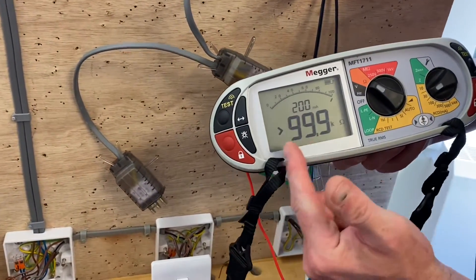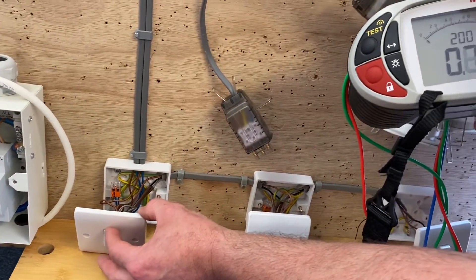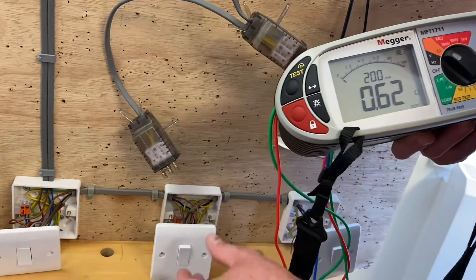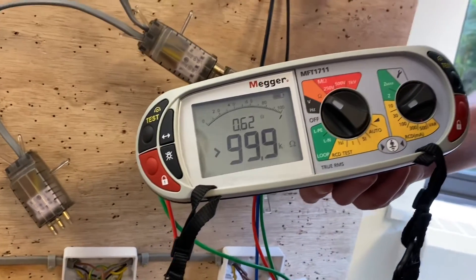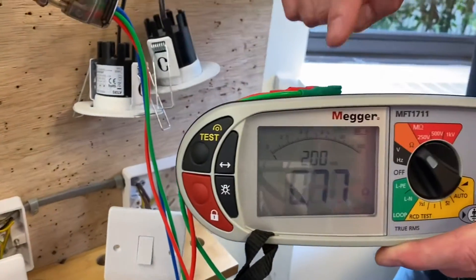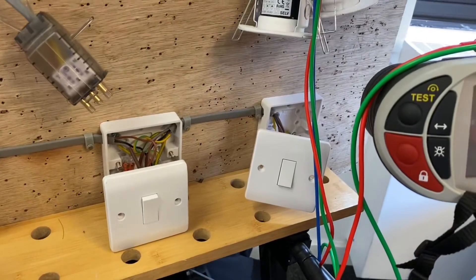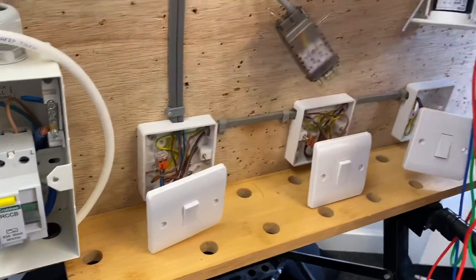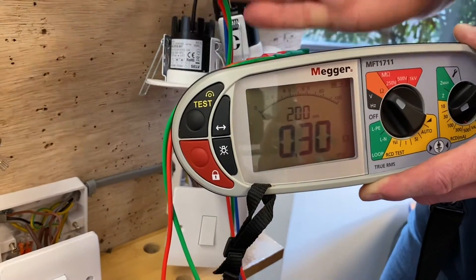At the next downlight we initially have an open circuit, so we press the first two-way switch and get a reading of 0.62 ohms. Operating the intermediate switch takes it to open circuit. Operating the two-way switch gives 0.77 ohms. Operating the intermediate again gives open circuit. Operating the final two-way switch gives 0.3 ohms. Our highest reading is still 1.2 ohms from the first test.